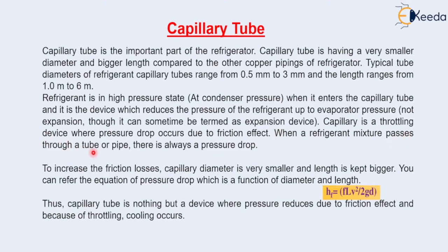When a refrigerant mixture passes through a tube or pipe, there is always a pressure drop. The equation H_f = fLV² / (2gD) shows that head loss is directly proportional to length and inversely proportional to diameter. If the diameter is very small, head loss will be more; if the length is more, head loss will also be more. So to increase friction losses, the capillary diameter is kept very small and the length is kept large.